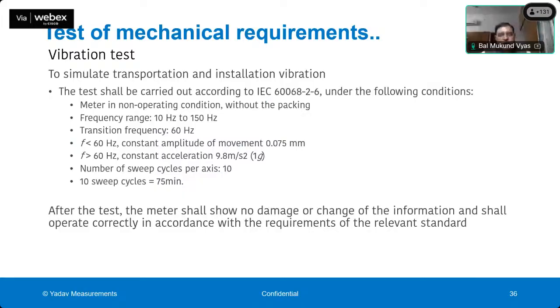Of course, then the meter is subjected to the vibration test, because when the meter is being transported, or sometimes even when the meter is installed, there can be vibration at the installation site also. Suppose it is installed in an industry or a commercial environment, or there is transportation vibration and so on. So the meter should withstand it, and its accuracy and its performance should not get affected because of this vibration. The transportation vibration which is specified is 10 Hertz to 150 Hertz with a transition frequency of 60 Hertz, which is for constant amplitude and constant acceleration.